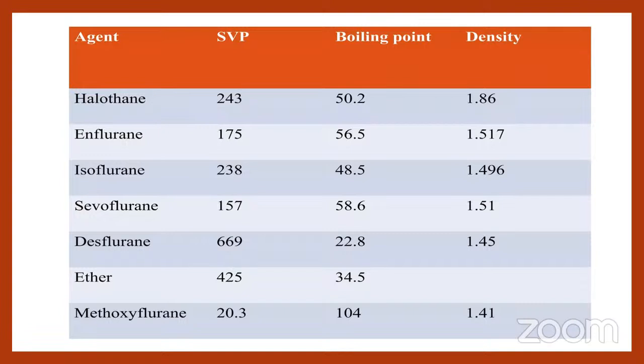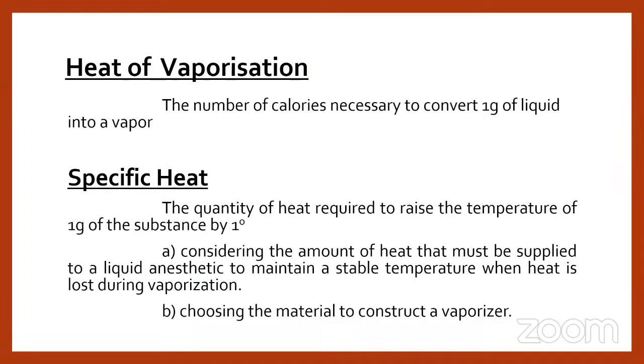So desflurane has the lowest boiling point of the anesthetic agents that we commonly use, which is 22.8 degrees centigrade, and methoxyflurane has the highest boiling point, 104 degrees centigrade, among the available anesthetic agents that we commonly use. Heat of vaporization, the number of calories required to convert 1 gram of liquid into vapor, is called heat of vaporization.